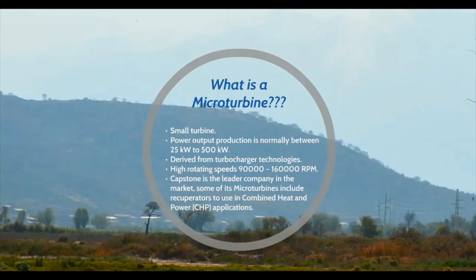In this section we are going to talk about microturbines. A microturbine is a small turbine with a power output between 25 to 500 kW. Microturbines were derived from turbocharger technologies found in large trucks or the turbines in aircraft auxiliary power units. Most microturbines are single-stage radial flow devices with high rotating speeds of 90,000 to 160,000 revolutions per minute. However, a few manufacturers have developed alternative systems with multiple stages or lower rotation speeds.